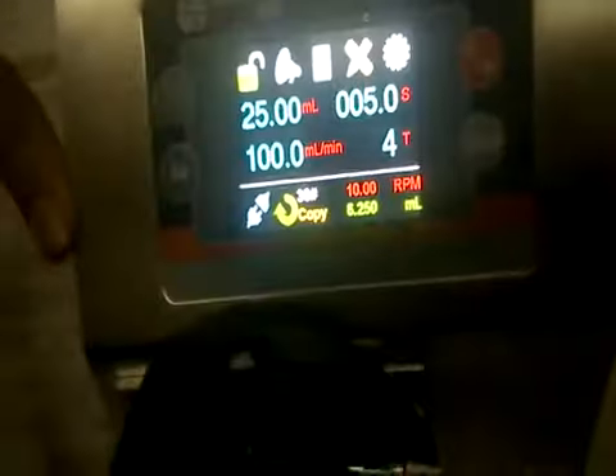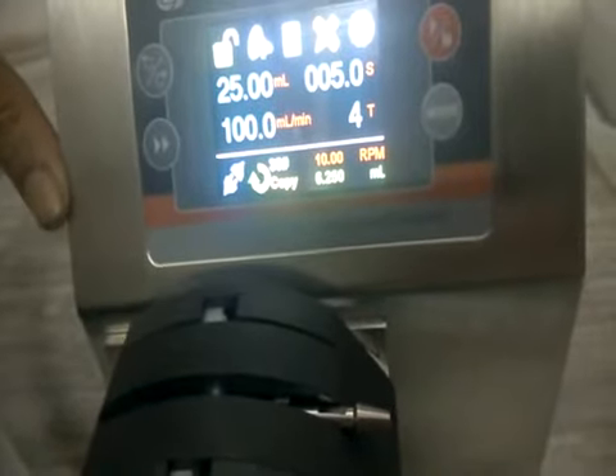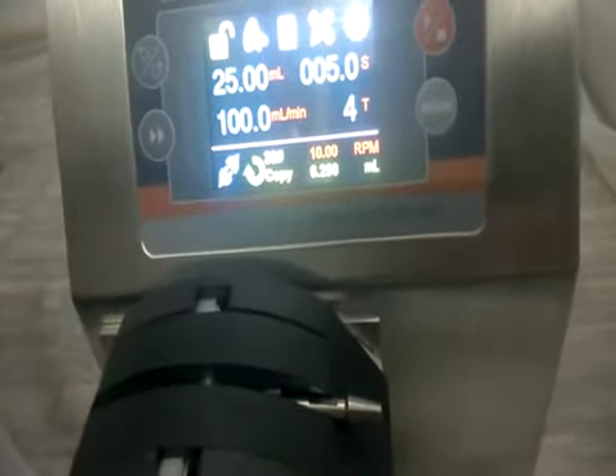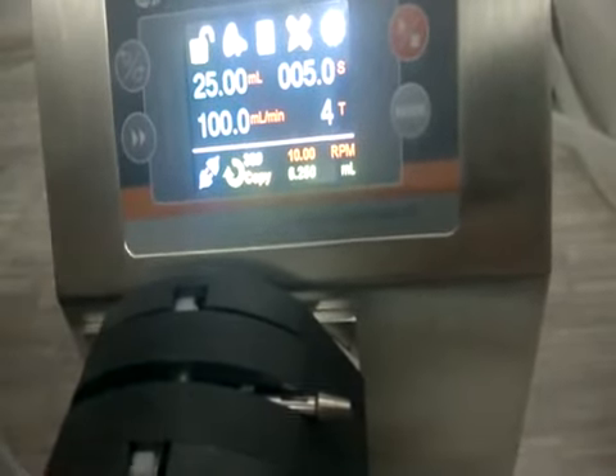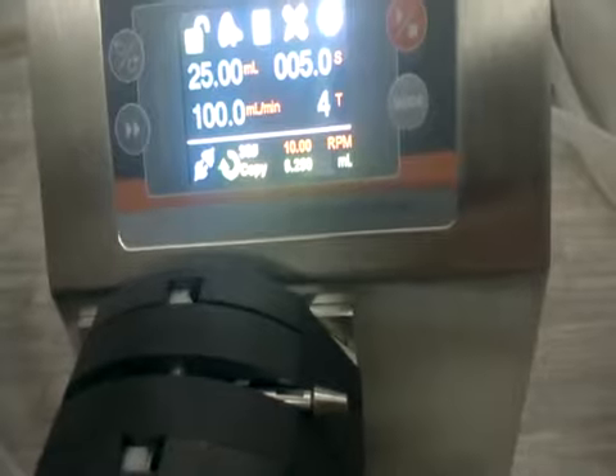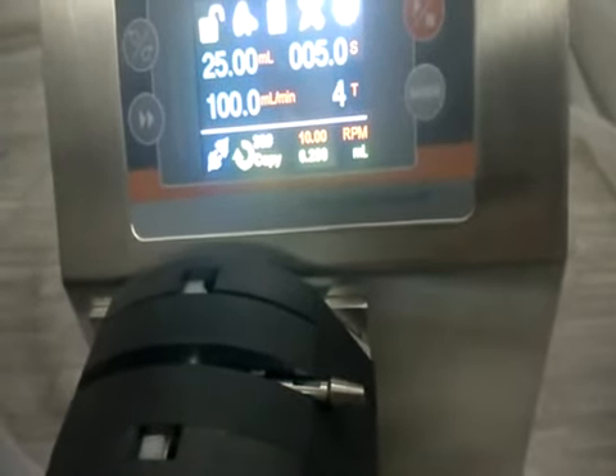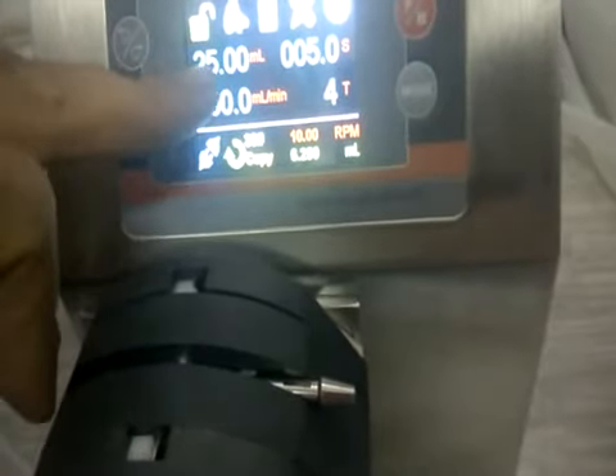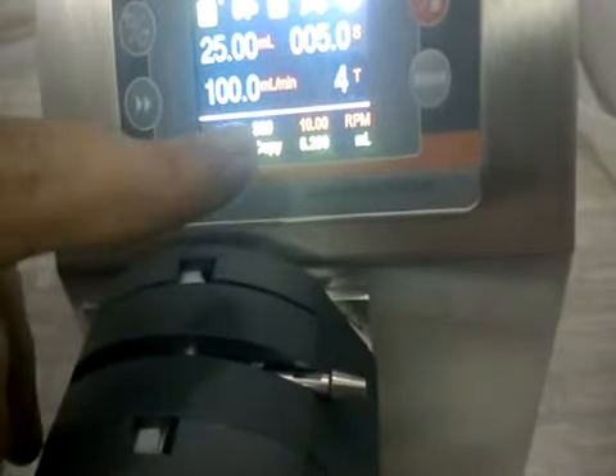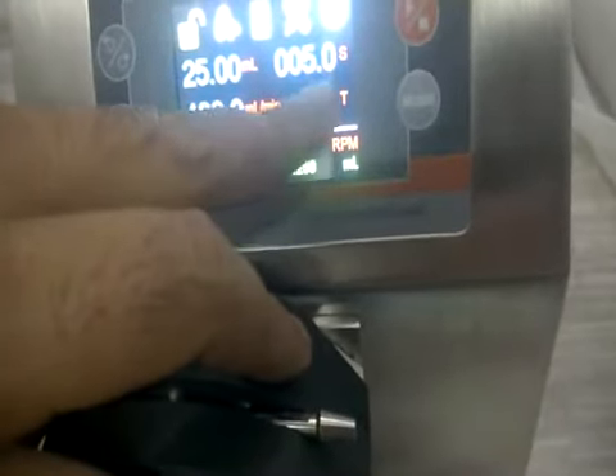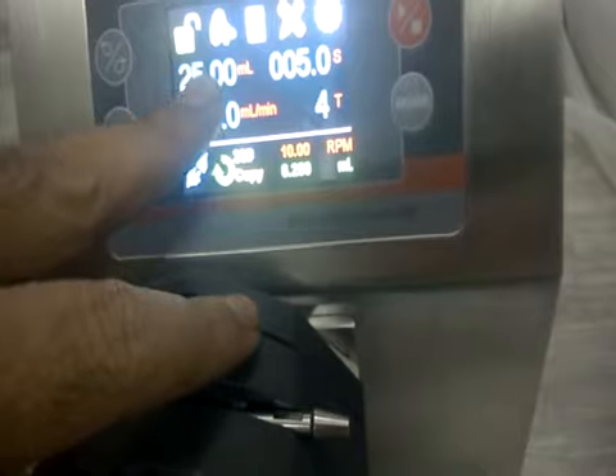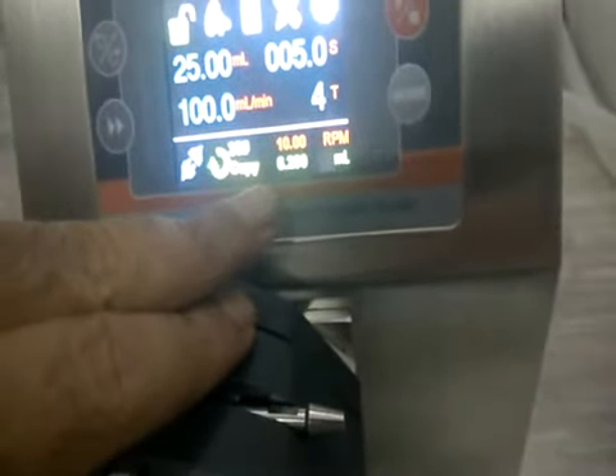And then the last function is copy. Copy is again an interesting function. Suppose you want to dispense 100 ml and you want to split 100 ml per minute into say 4 parts. So you want to dispense 25 ml, and the time gap is 5 seconds. After each cycle it will wait for 5 seconds. So it will dispense 25 ml, then wait, then 25 ml, then wait. It will dispense 25 ml in 4 cycles.